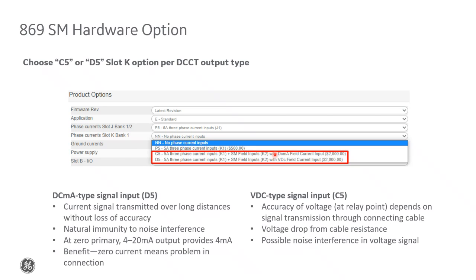The selection here is based on whether your DC CT will have a DC milliamp output, or a volts DC output. Just a note, when you order this option, we do provide the voltage divider card to step down the field inputs, but you do need to separately get a new DC-CT. We do have specific ranges that we can provide to you to assist in the DC-CT selection, or we can recommend to you a specific model, or we can even provide it additionally in the package.